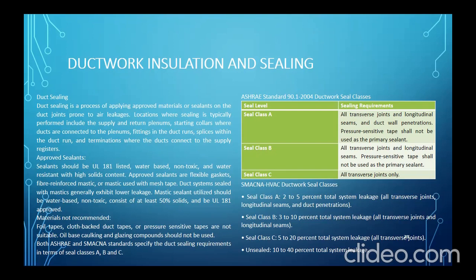Foil tapes, cloth-backed duct tapes, or pressure-sensitive tapes are not suitable yung pang seal. So, oil-based caulking and glazing compounds should not be used. Sa pipe yata to. Both ASHRAE and SMACNA standards specify the duct sealing requirements in terms of seal classes A, B, and C. So, ito yung seal classes or label. So, seal class A, yung mga requirements mo, is for all transverse joints, longitudinal seams, and duct wall penetrations. Transverse joints yung across, yung longitudinal yung sa length, yung sa haba ng duct.